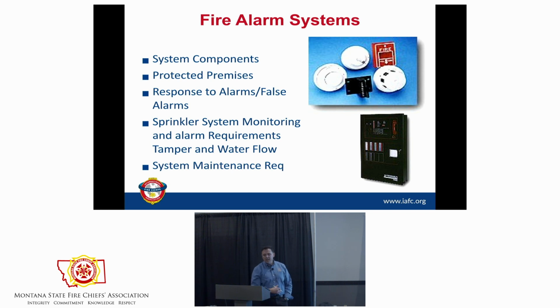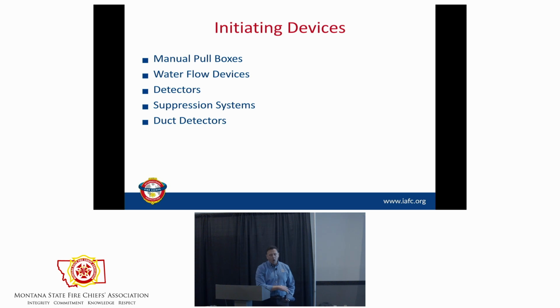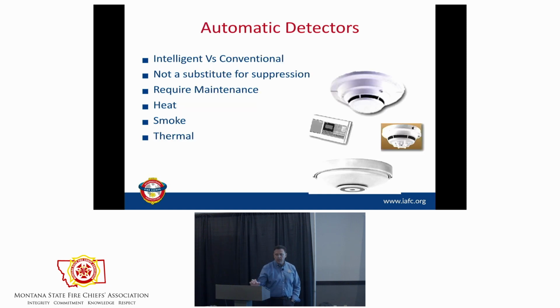And so we're starting to see more and more replacements. But really, they have all these things that can make a fire alarm go: fire box, manual pull boxes, water flow detectors, suppression system, duct smoke detectors. In our world, duct smoke detection is what's called a supervisory signal. It doesn't call the fire department. We don't want to know. If we did, we'd be going on hundreds of alarms. It's really intended to do what? Alert the occupant.